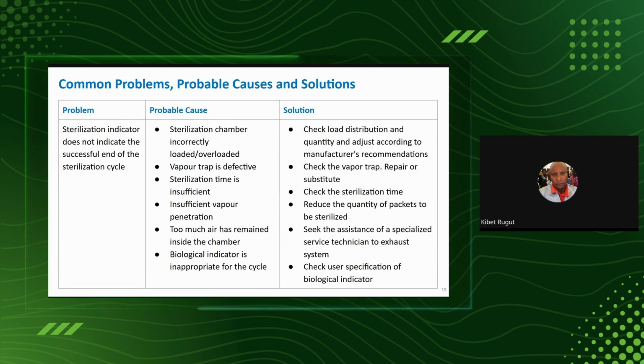So try to follow the set times for the right equipment. Again, the quantities of packets to be sterilized: there is a guide on how much you should load in every cycle. And when you have any problem, you can also call a specialized technician to clean up the system, and then you will have your running very smooth. For biological indicators, I'm sure the sterilization profession will guide us on which ones to pick.